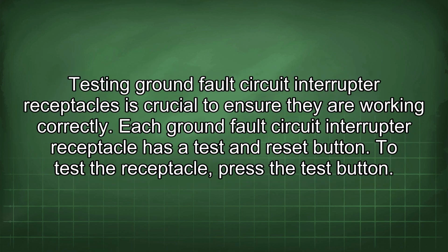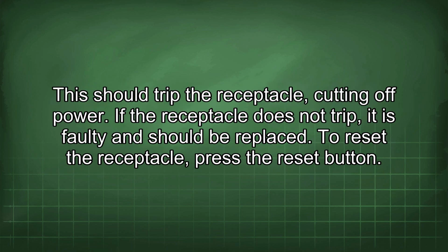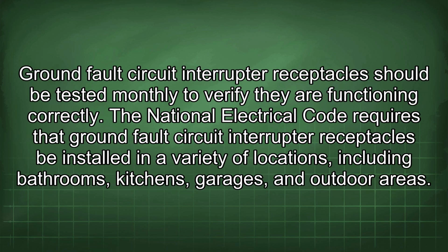Testing ground fault circuit interrupter receptacles is crucial to ensure they are working correctly. Each ground fault circuit interrupter receptacle has a test and reset button. To test the receptacle, press the test button. This should trip the receptacle, cutting off power. If the receptacle does not trip, it is faulty and should be replaced. To reset the receptacle, press the reset button. Ground fault circuit interrupter receptacles should be tested monthly to verify they are functioning correctly.